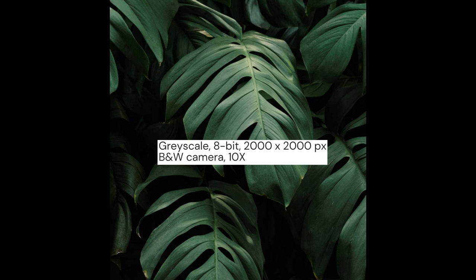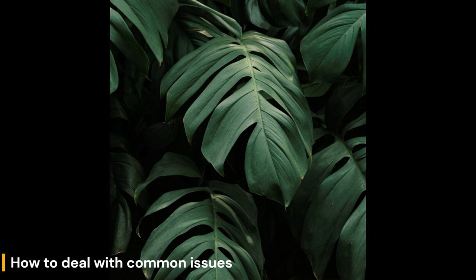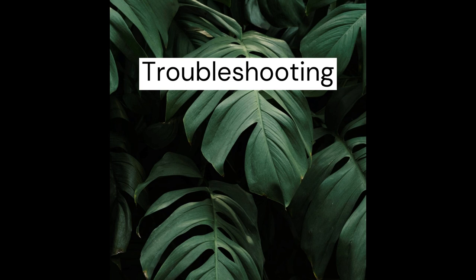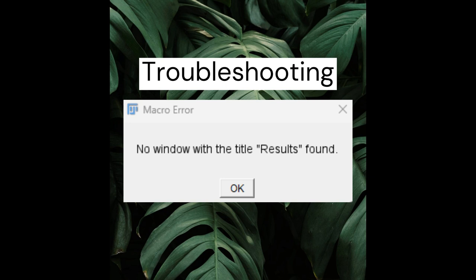Normally there should be no issues with installation of both packages, but if you find some, reach us and we will try to help you. Be aware that these packages were developed and tested on Windows, so we cannot certify that it will work on another OS properly. Here I summarize a few known issues you might encounter during macro execution. First, you might see a text box saying there is no result window open — this is a temporization issue. If Fiji is navigating with different packages in different programming languages, there will still be some timing issues depending on machine performance and the time it takes to load the plugin.